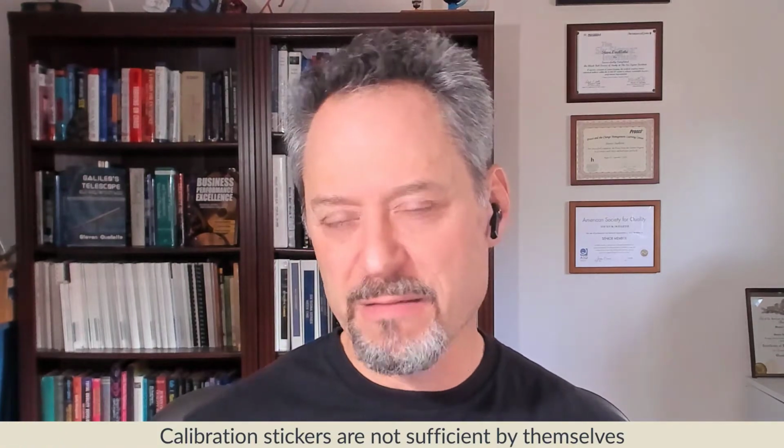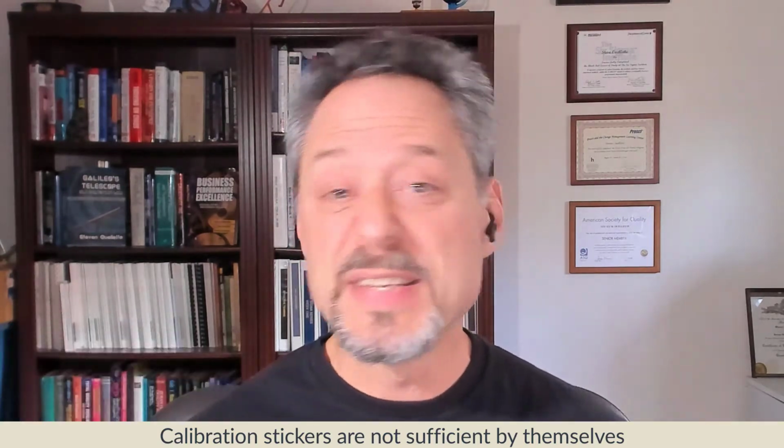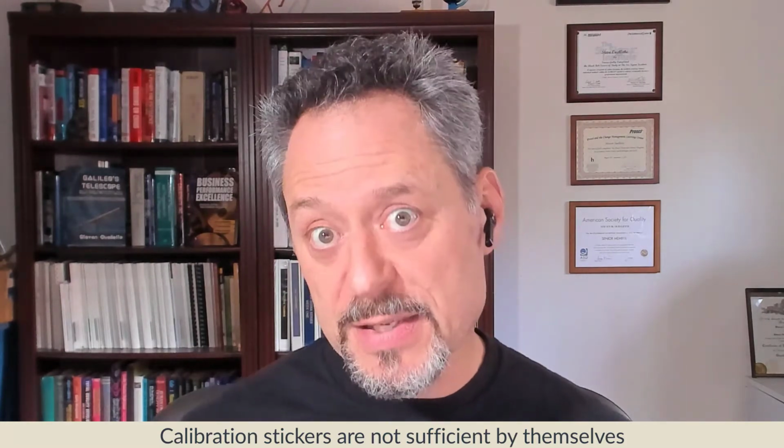Now, any measuring device needs to show that it has control, precision, and accuracy. Control is stability through time. Precision is how much variability there is in measuring the same thing over and over again. And accuracy is how close to the true number I am actually getting. So something like a calibration sticker isn't sufficient for that, right? That says that at some point, 5 months in the past, this device could measure this gauge block, which probably isn't even like the thing that we're making.